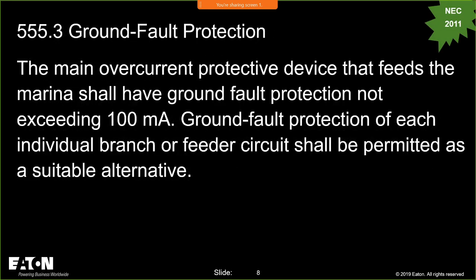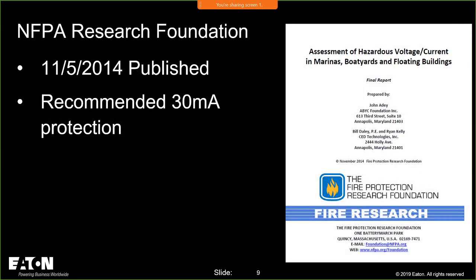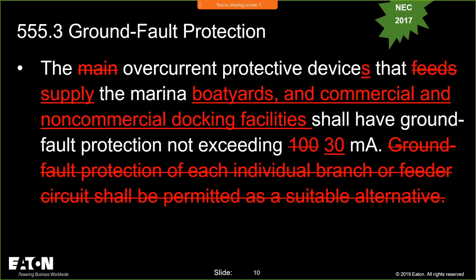Because of those things that happened in the '11 cycle, that initiated a research foundation study that was put into place. They recommended reducing that 100 milliamps down to 30 milliamps. That happened in the '17 cycle. That was a bit of an issue, because 30 milliamps at the service equipment presented a challenge.